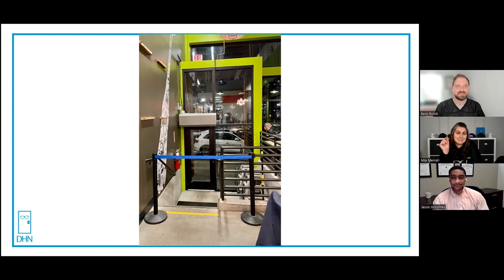I'm at an 8 because right now it's non-compliant, but it can be fixed. It could be fixed momentarily, except for that exit sign. I don't care if they got that approved. That's terrible placement. You're never going to see that in an actual emergency.